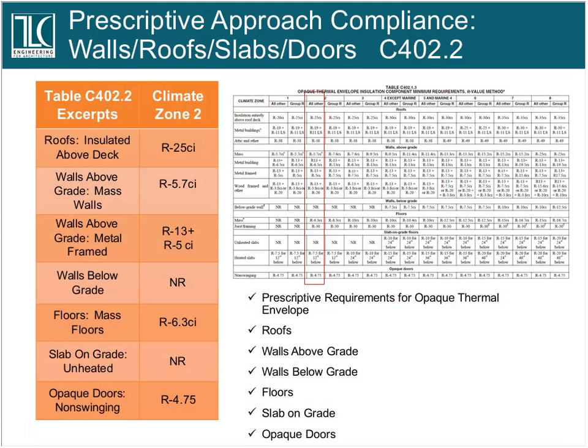This eye chart that you're seeing here is actually a snip from the code that shows us the required R values for each one of the climate zones, whether the building's residential characteristics or non-residential. And then I've taken the climate zone 2, the Gulf Coast states, out and let you see what is being required there. The roofing insulation has gone from R20 up to R25, while the frame walls, metal frame above grade walls, used to be 2x4 metal studs on 16-inch centers with 4-inch R13 bats between them. Now that's had an R5 continuous insulation blue board, if you will, on the outside face of those studs. So there's now a requirement for that continuous insulation layer that we have never seen in this climate zone before.